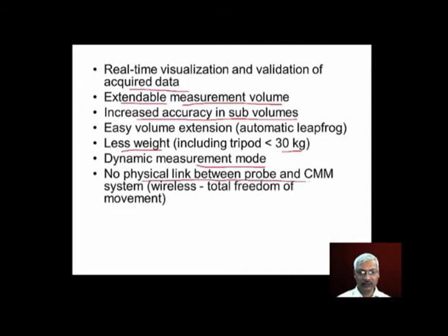And there is a real-time visualization and validation of acquired data. The measurement volume can be extended depending upon the requirement. Increased accuracy in the sub-volumes is possible. Easy volume extension by automatic leapfrog system, and the total system weight is very less, including the tripod it is less than 30 kg. A dynamic measurement mode is possible. There is no physical link between probe and CMM system, hence there is total freedom of movement for the operator.